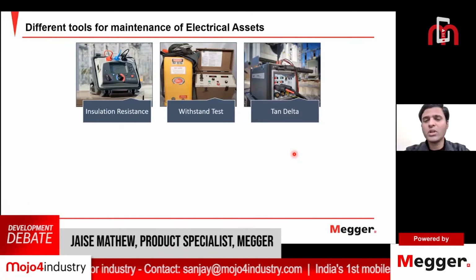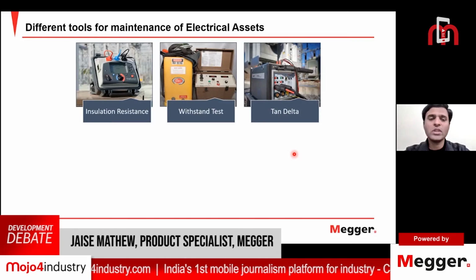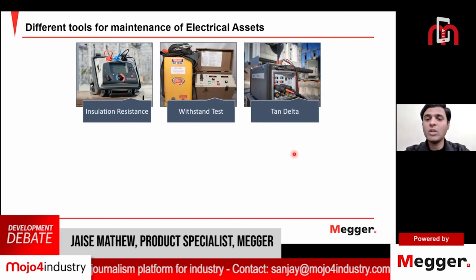Nowadays, there is a trend of using tan delta measurement on electrical assets. So what does a tan delta measurement do? It injects an AC voltage. As we have seen, the IR test and the withstand test use a DC source. However, in the tan delta measurement, an AC source is used, which helps to do the testing in the actual condition of that particular asset.